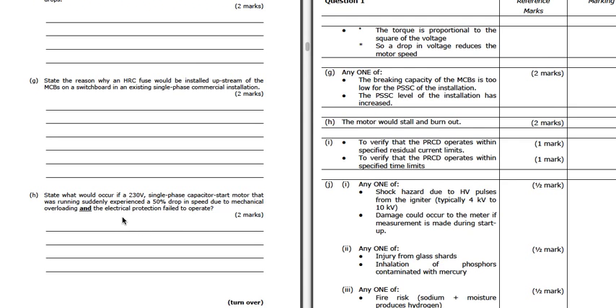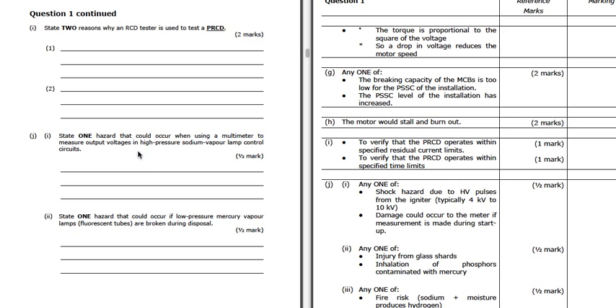H, state what would occur if a 230 volt single phase capacitor start motor that was running suddenly experienced a 50% drop in speed due to mechanical overload. So something's jamming, if you like, the speed has fallen and the protection has failed to operate. So the motor is going to stall and burn out. It's because we've got that less cooling effect, it's going to have more current and it's going to burn out the windings.